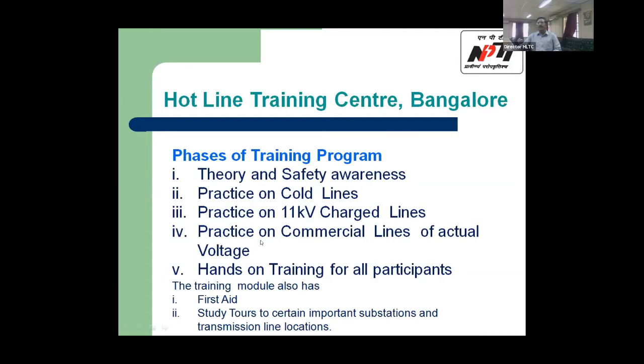In the final stage, the last leg of the training, we take them to commercial lines at actual voltage of KPTCL or Power Grid, depending on the voltage level. Up to 220 kV, they are normally given practice on Karnataka Power Transmission Corporation Limited lines. For 400 kV, we take them to Power Grid (PGCIL) lines.